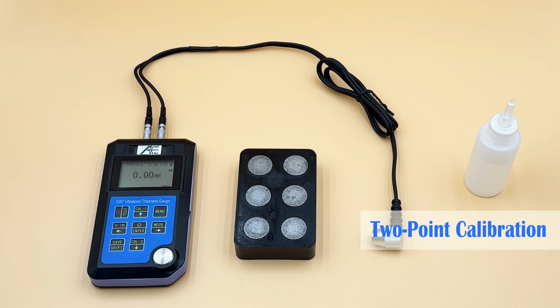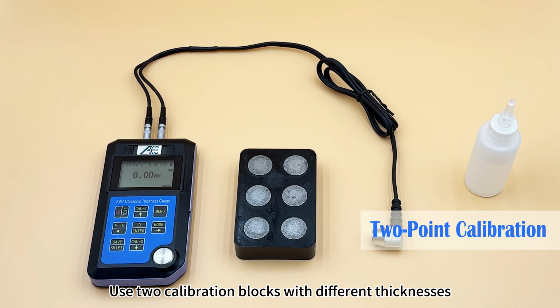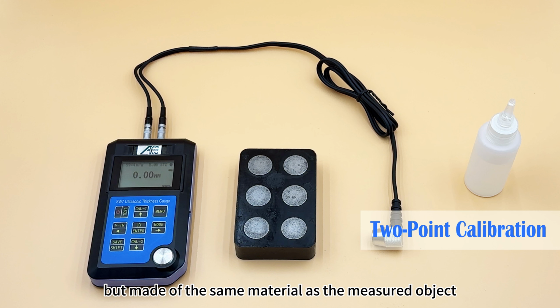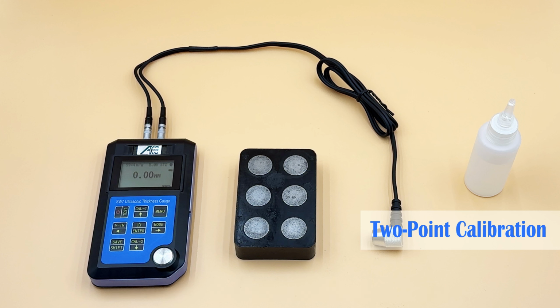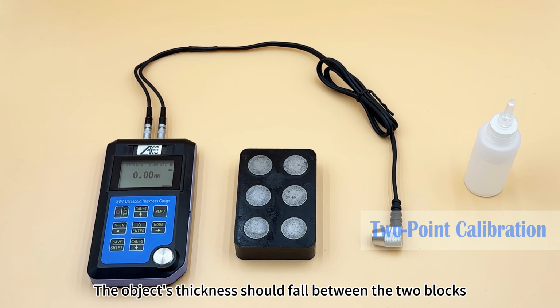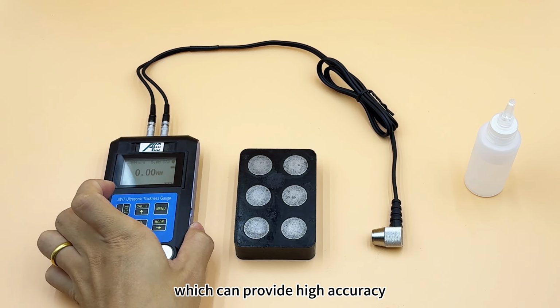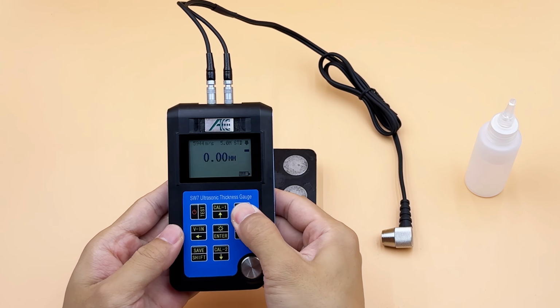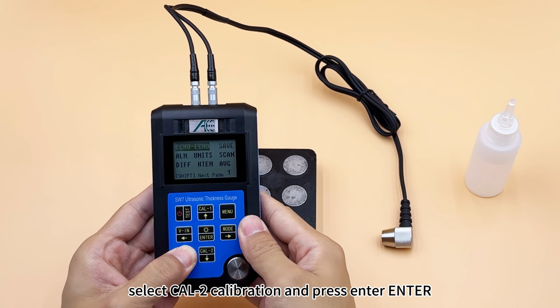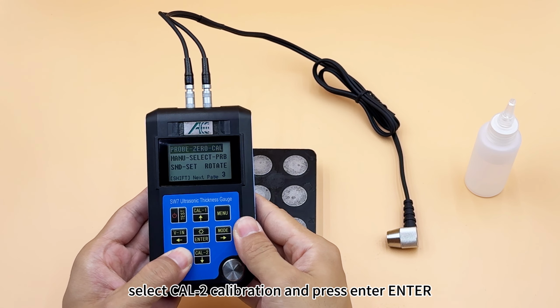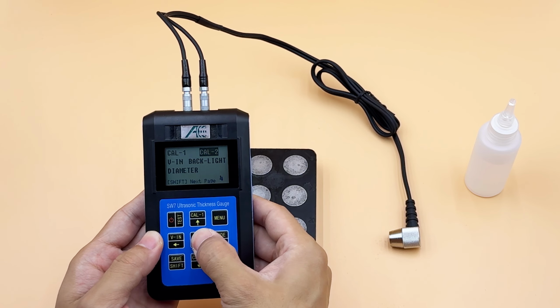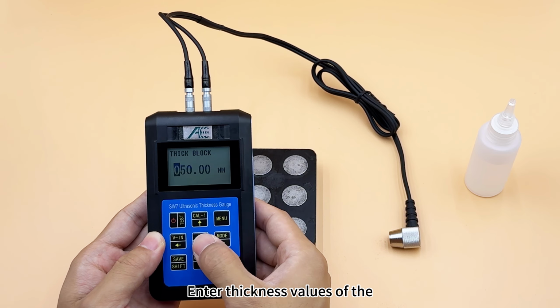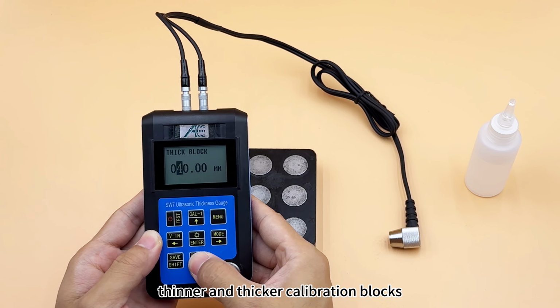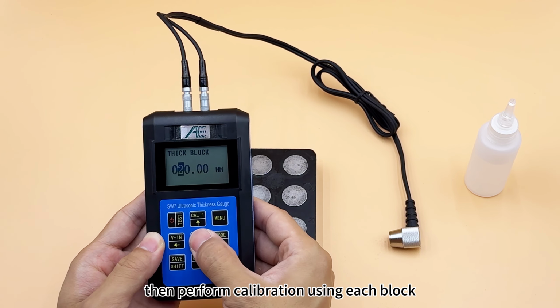Two-point calibration. Use 2 calibration blocks with different thicknesses but made of the same material as the measured object. The object's thickness should fall between the 2 blocks, which can provide high accuracy. Press menu and shift key, select Cal 2 calibration, and press enter. Enter thickness values of the thinner and thicker calibration blocks, then perform calibration using each block.